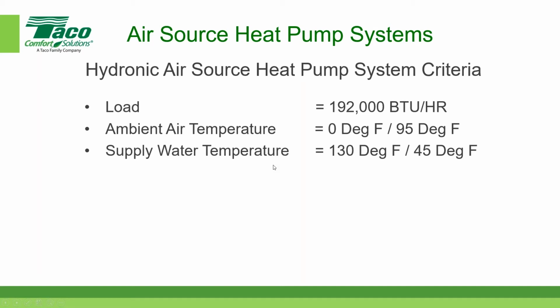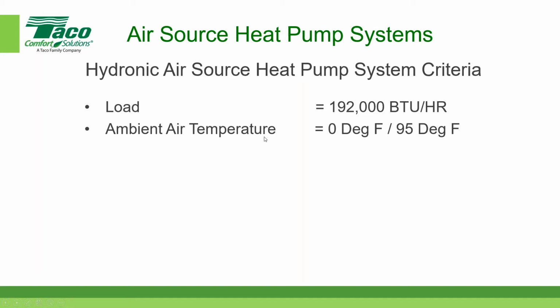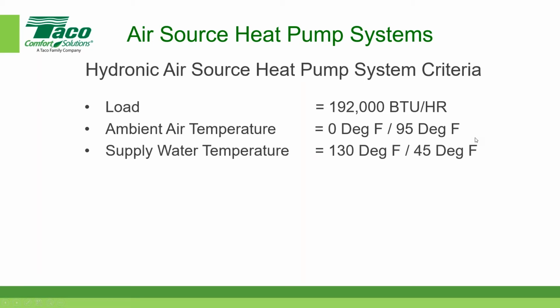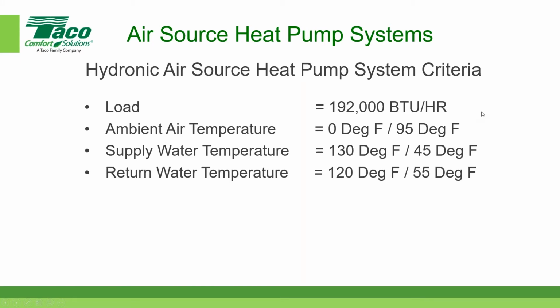The ambient air is the outside air. That's the temperature. I'm going to extract heat from 0 degrees Fahrenheit air in the winter, and I'm going to reject heat to 95 degree ambient air in the summer. Supply water temperature for winter operation is 130 degrees Fahrenheit. For summer operation it is 45 degrees Fahrenheit. And the return water temperature is 120 for the heating season and 55 for the cooling season. In both cases, it's a 10 degree delta T.